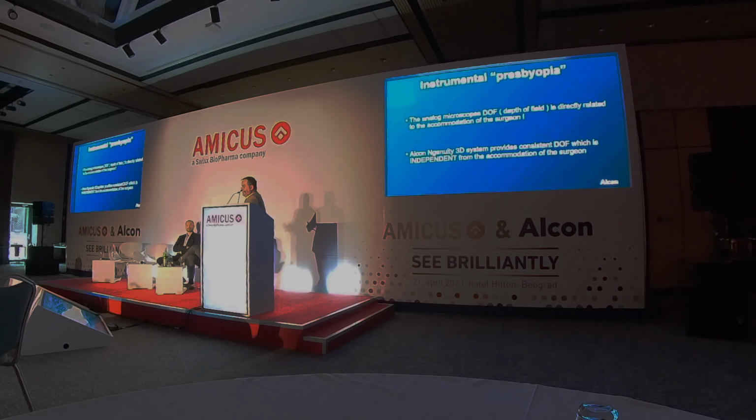Sorry to say, but elder surgeons are refocusing more because they have a shallow depth of field. What is important with the Ngenuity is that it provides a consistent depth of focus, which is absolutely independent of the presbyopia of the surgeon. Why? Because the screen of the Ngenuity is more like far vision than near vision. So it's a small detail which is quite important to understand how to use the system.